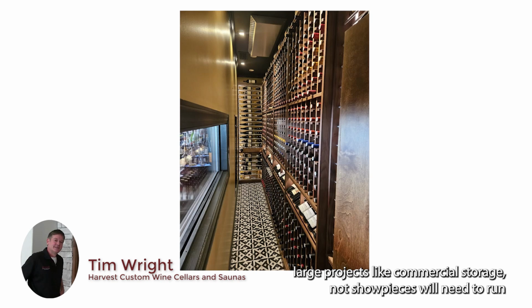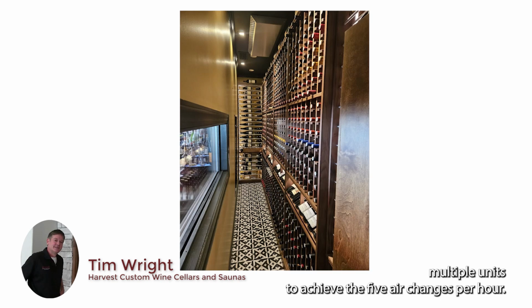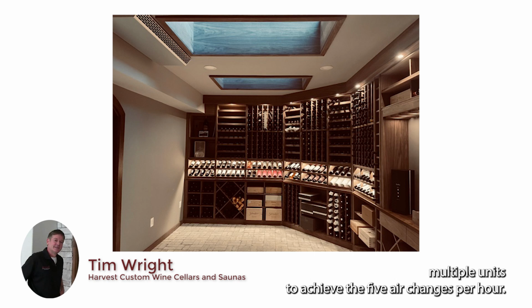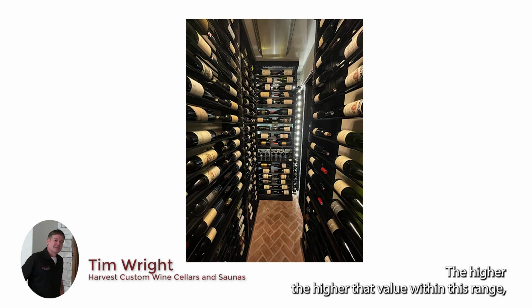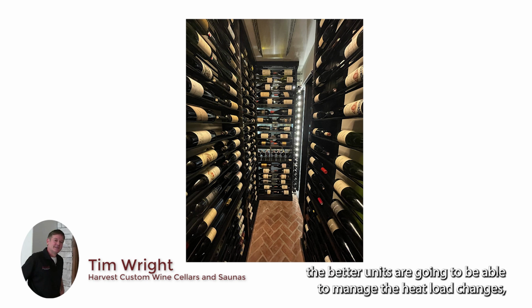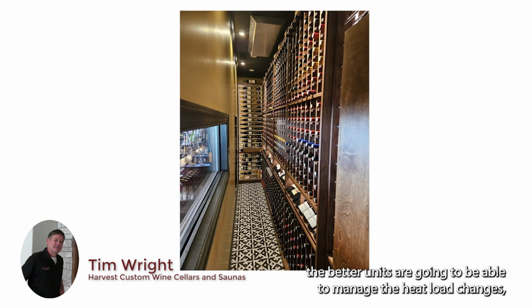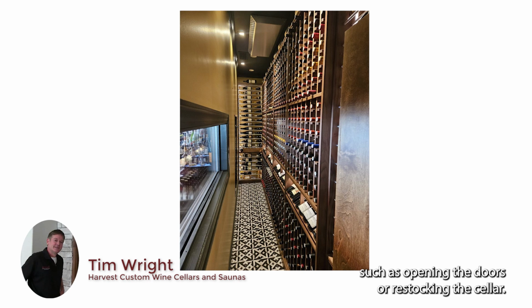So most large projects like commercial storage, not showpieces, will need to run multiple units to achieve the 5 air exchanges per hour. The higher that value within this range, the better a unit's going to be able to manage the heat load changes, such as opening the doors or restocking the cellar.